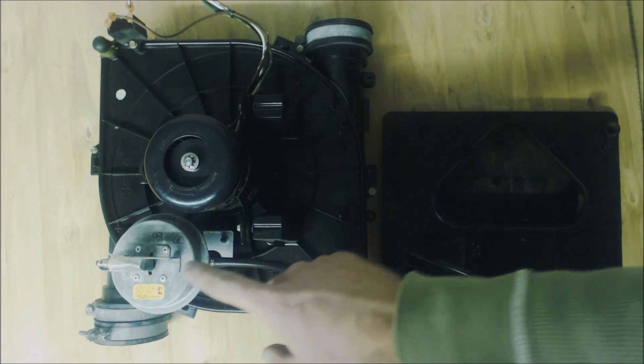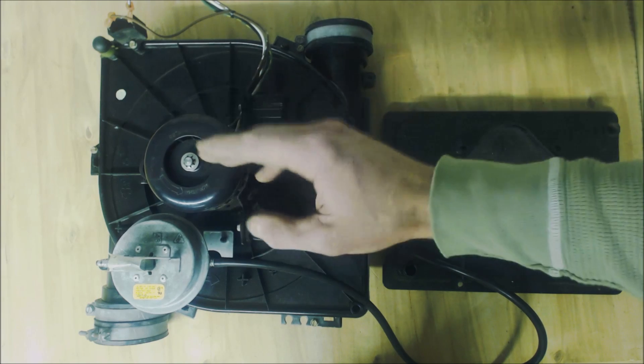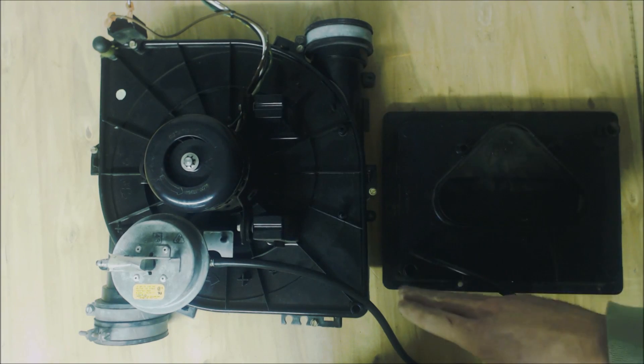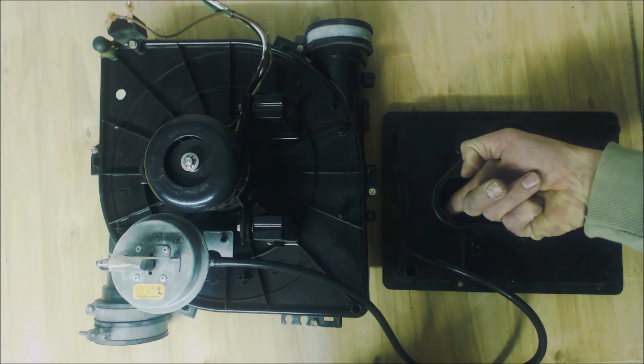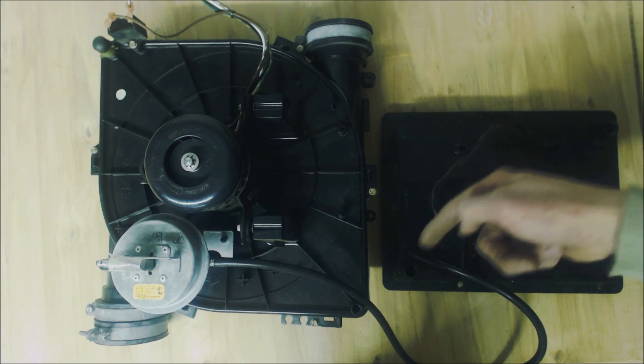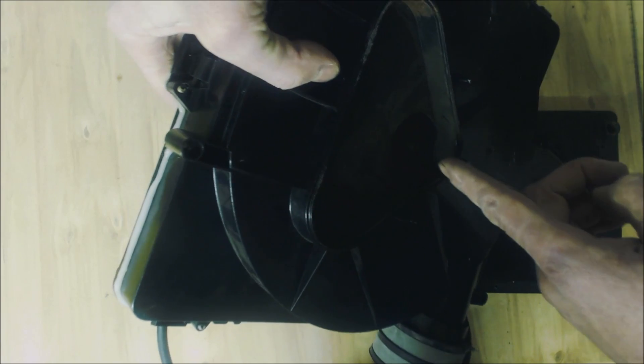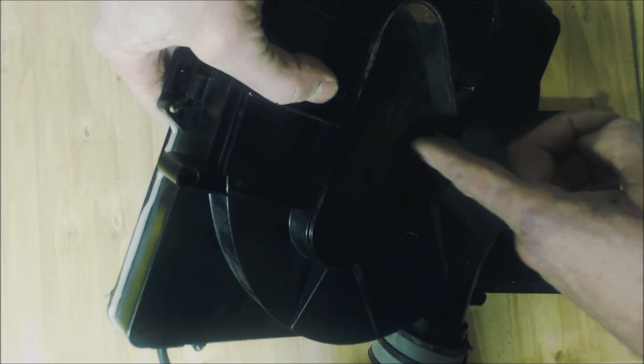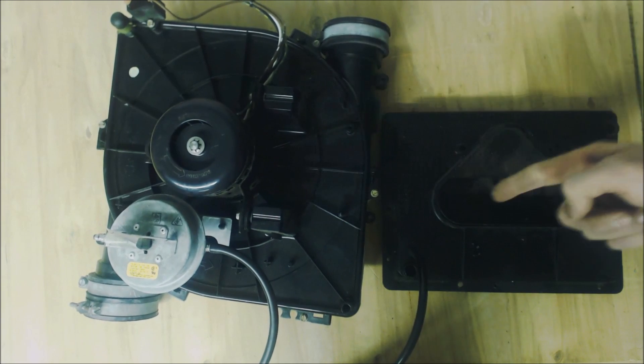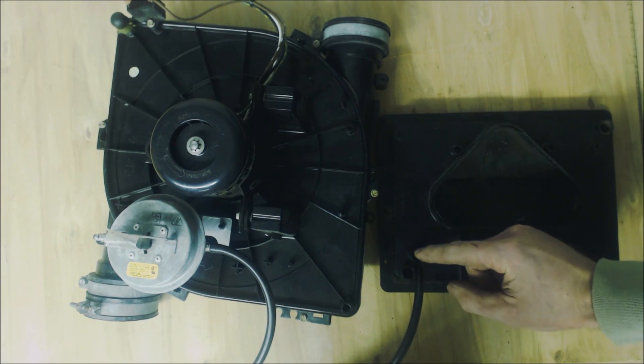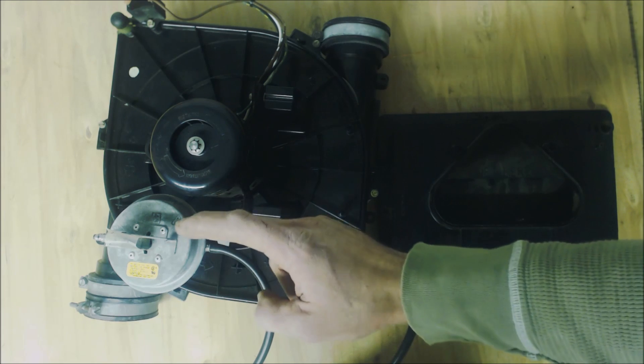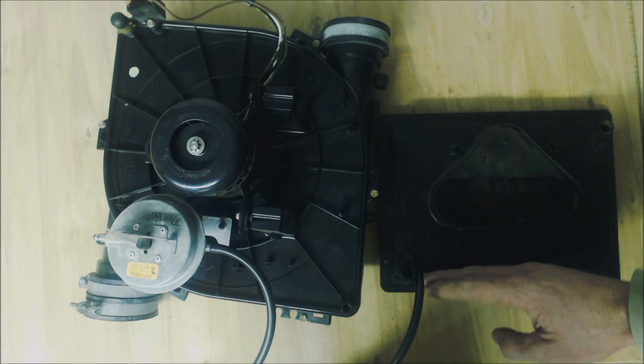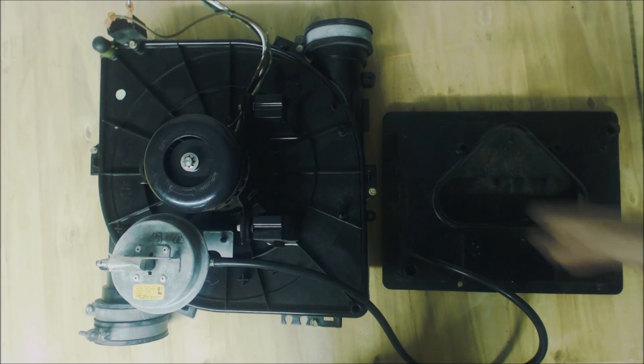Just remember that this pressure switch will not read the negative pressure from the inducer motor running if this is filled up with water, because your inducer motor is basically coming from here and then this is where you're reading it at. This is the back of the inducer motor and your negative pressure is coming from right in here, and it's coming in here and that's where your pressure switch is receiving that negative pressure. If the water level's too high, then it will not read this negative pressure.